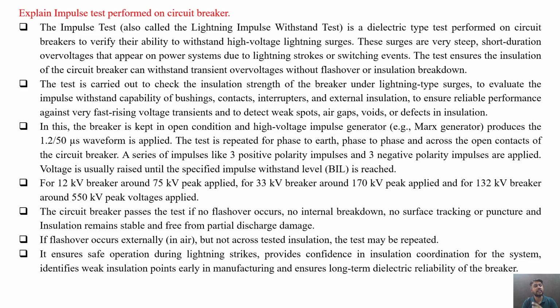to evaluate the impulse withstand capability of the bushings, contacts, interrupters and external insulation. Also to ensure reliable performance against very fast rising voltage transients and to detect the weak spots, or say the hot spots, air gaps, voids, that is the deformation points or defects in the insulation.